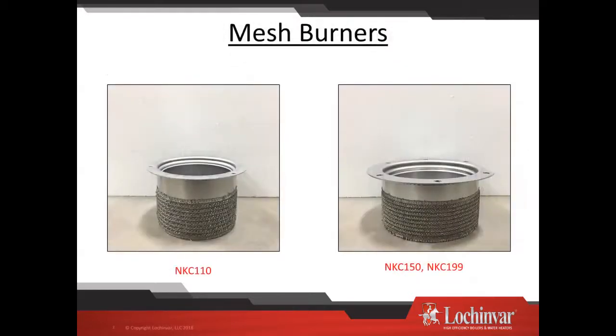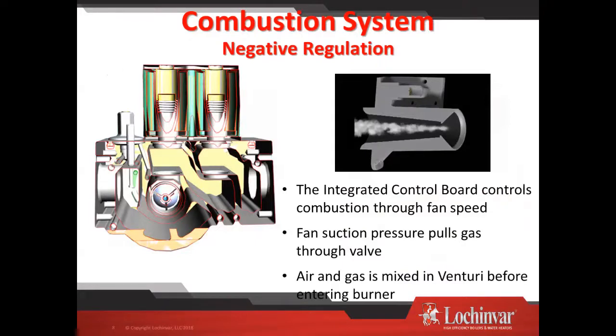The mesh burners of the combi unit. It's a burner we use really throughout many of the boilers within the product line, and we'll talk about cleaning that today. But here's where I want to talk to really in this is the combustion system. So it's a negative regulation combustion system. What does that mean? Negative regulation really means that I am relying on the air movement that my fan pulls across the orifices within my venturi to draw the gas in, make the mixture, and off we go. Awful lot of words to say that the fan suction draws the gas into the combustion chamber, and off we go.